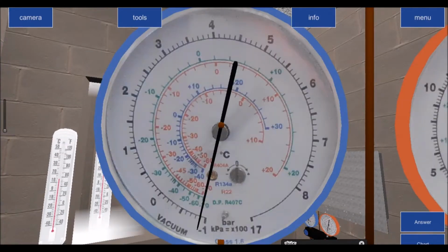Look, so this is my slide chart. This is my pressure temperature slide chart. So we've got pressure going up along, and we've got temperature for the different refrigerants: 407C, R22, 134A and 404A, okay? So depending on the refrigerant that's in the system, for every temperature there's a corresponding pressure, or for every pressure there's a corresponding temperature.